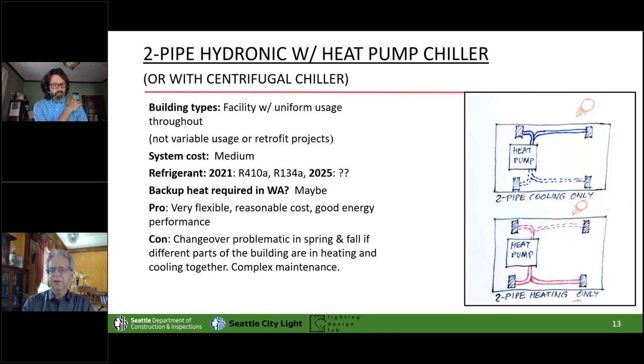And it's also worth saying it's the first time we've said heat pump chiller. So think chiller, same thing that's always made cool hydronic fluid moving around your building. We just use it like a heat pump. Like I said, that's a couple valves, not magic. I shouldn't undersell the design. There's some real equipment design in there. But as far as packaged equipment, it looks just like a chiller. It can also make hot water. It's a pretty neat thing. It can make hot water down to pretty low temperatures, and those are going down in a quick hurry too. So heat pump chillers, new thing.